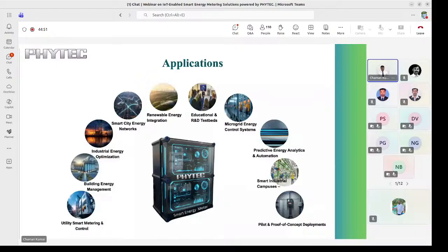So how will they turn off your load? They will send one command, a disconnect command, and it will come to the HES. It will go to the DCU. It will come to your meter, and then it will go to the load switch. The load switch has an electromagnetic switch that will turn off your load. That is how this basic smart meter architecture works.